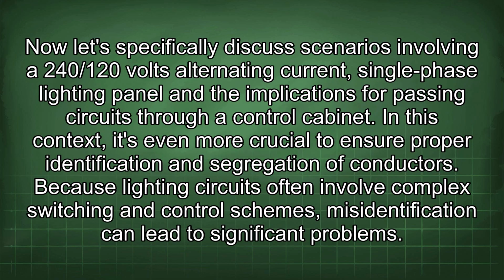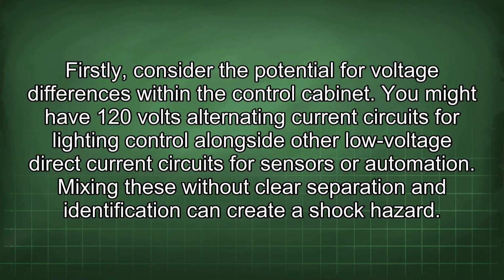Now let's specifically discuss scenarios involving a 240/120 volts alternating current, single-phase lighting panel, and the implications for passing circuits through a control cabinet. In this context, it's even more crucial to ensure proper identification and segregation of conductors. Because lighting circuits often involve complex switching and control schemes, misidentification can lead to significant problems. Firstly, consider the potential for voltage differences within the control cabinet. You might have 120 volts alternating current circuits for lighting control alongside other low voltage direct current circuits for sensors or automation. Mixing these without clear separation and identification can create a shock hazard.